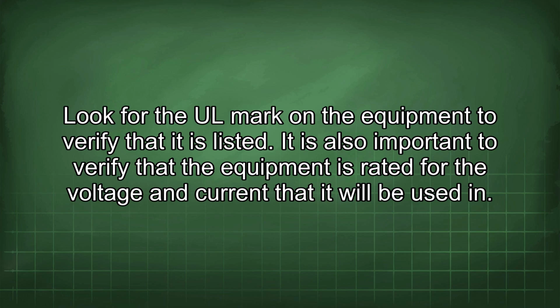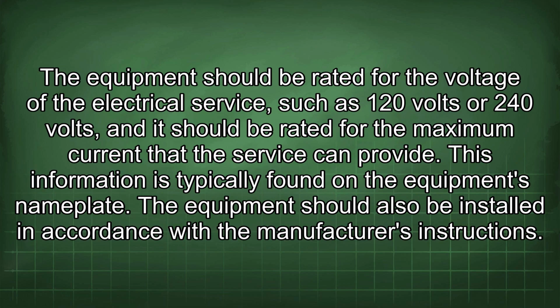It is also important to verify that the equipment is rated for the voltage and current that it will be used in. The equipment should be rated for the voltage of the electrical service, such as 120 volts or 240 volts, and it should be rated for the maximum current that the service can provide. This information is typically found on the equipment's nameplate.